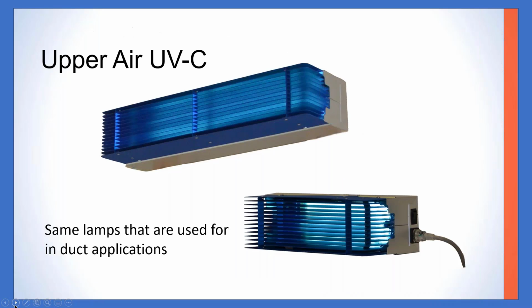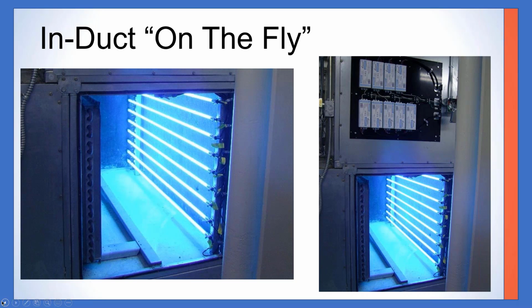This particular one here is, I'm going to go back, sorry, flipped ahead, a job at Lackland Air Force Base, and there's 160 air handling units where this particular system was designed for a 99.98% first pass kill of tuberculosis, a harder microbe to kill than the coronavirus. So in this particular case, what you have is airflow coming from the left and airflow going up. So it has to take a 90-degree turn up. So this is many more lamps than what we would see, almost double the number of lamps that you would see for a coronavirus. Tuberculosis is harder to kill, but also we had to design this particular system for a microbe possibly coming out of the top of this coil and then turning up and going straight up. So a very short residence time. The microbe coming out of the bottom and gets to see all of these lamps had a longer exposure time.